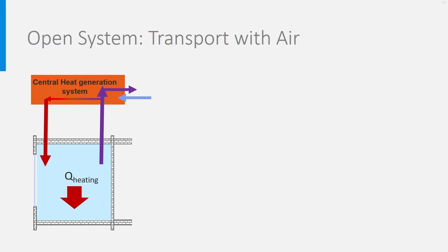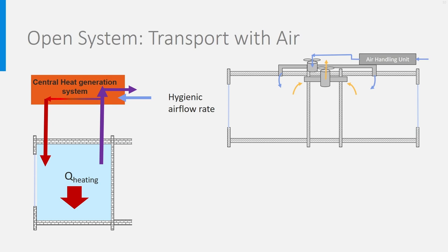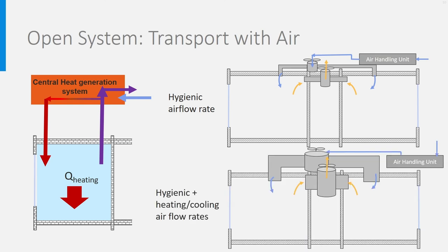Instead, open systems are chosen. The duct is open and ends in the room, delivering warm air which mixes with the room air and is exhausted back through a return pipe — exactly like a mechanical supply and exhaust ventilation system. The only problem is that the volume flow rate of hygienic air is much lower than the flow rate needed to bring heat or cold into the room. So the mechanical ventilation system must be much bigger and the ducts much larger — with important consequences for the architect who needs to reserve enough space.